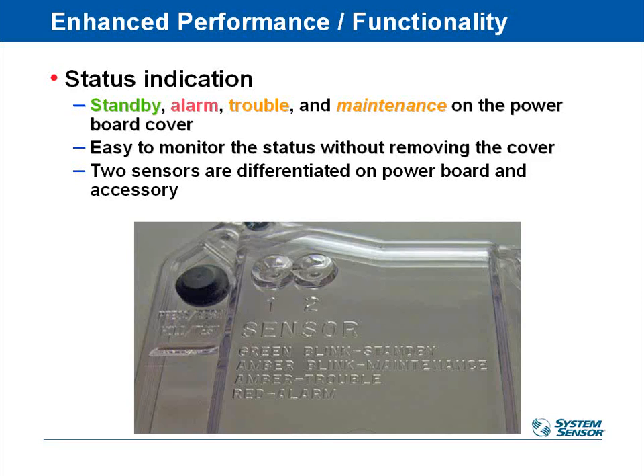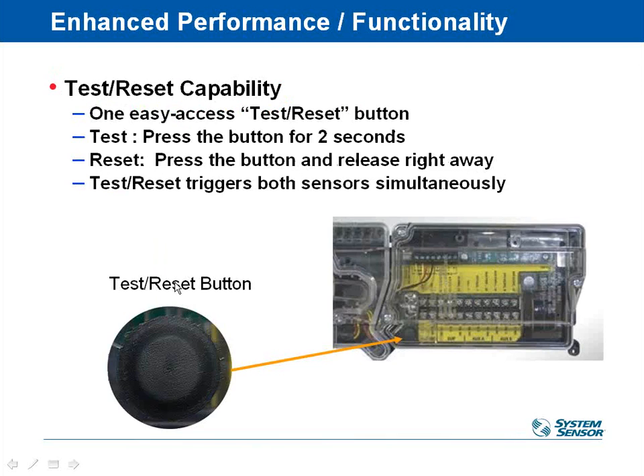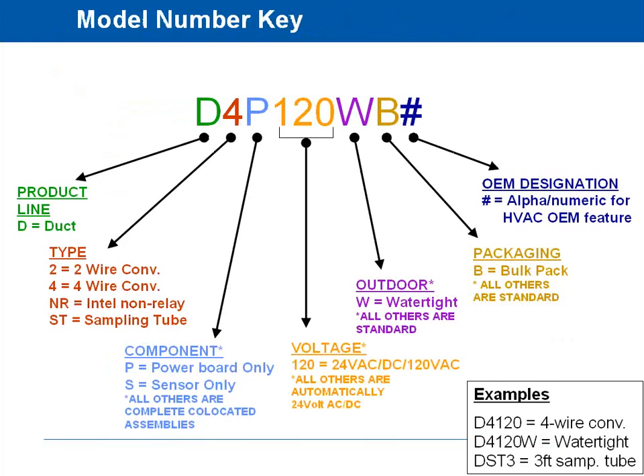The front of the plastic is nice because it's clear, so I can see what's going on, with the exception of the watertight one. You can't see through that one, but the normal detector is clear. You can see what's going on. You can see the sensor lights on it. You can access the remote test button, which is this black button here, from outside the plastic cover, so you don't have to take the cover off even to do a test, which is very helpful.